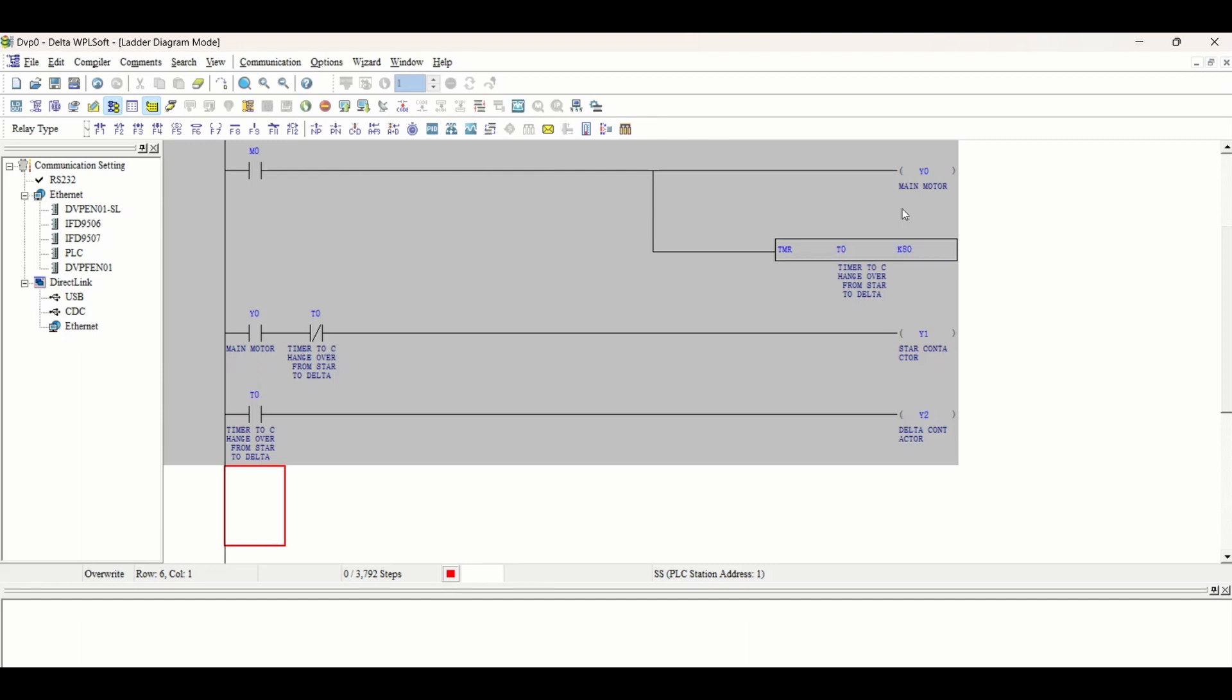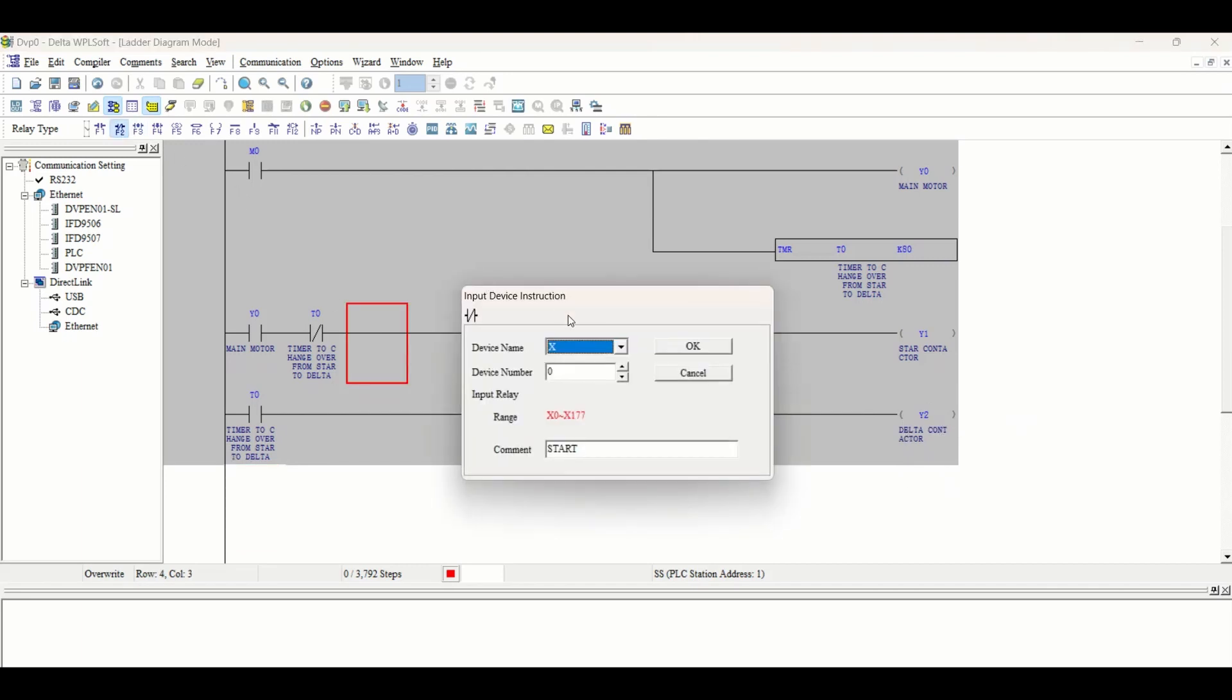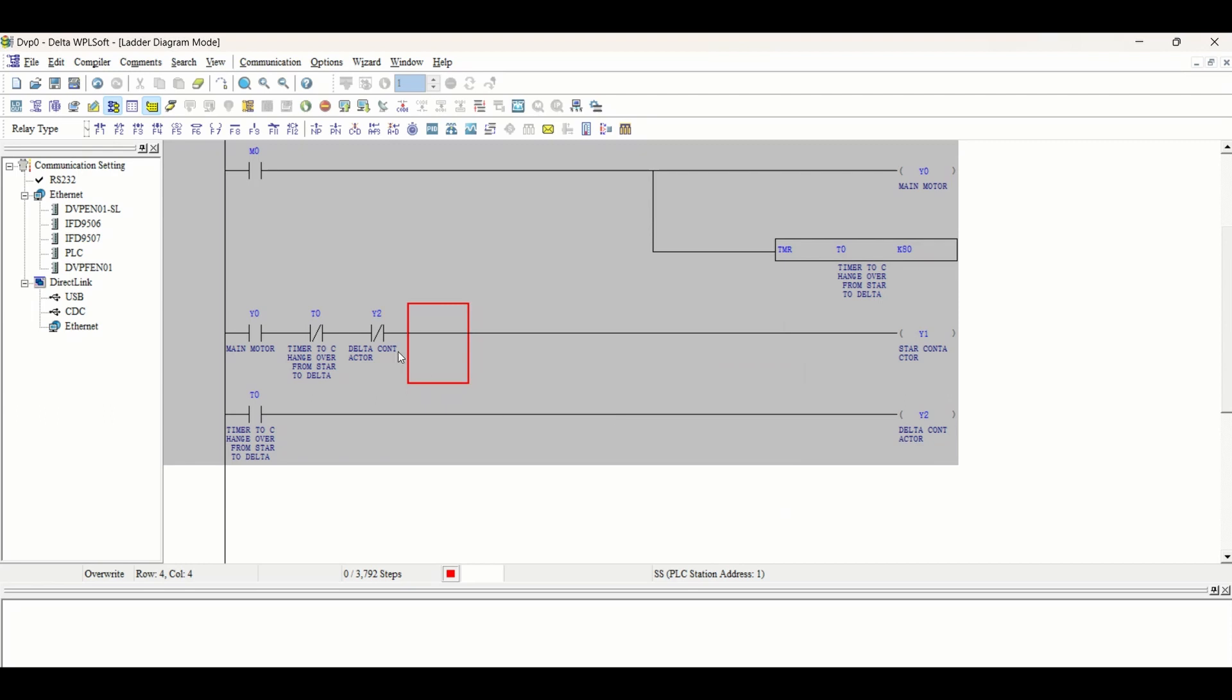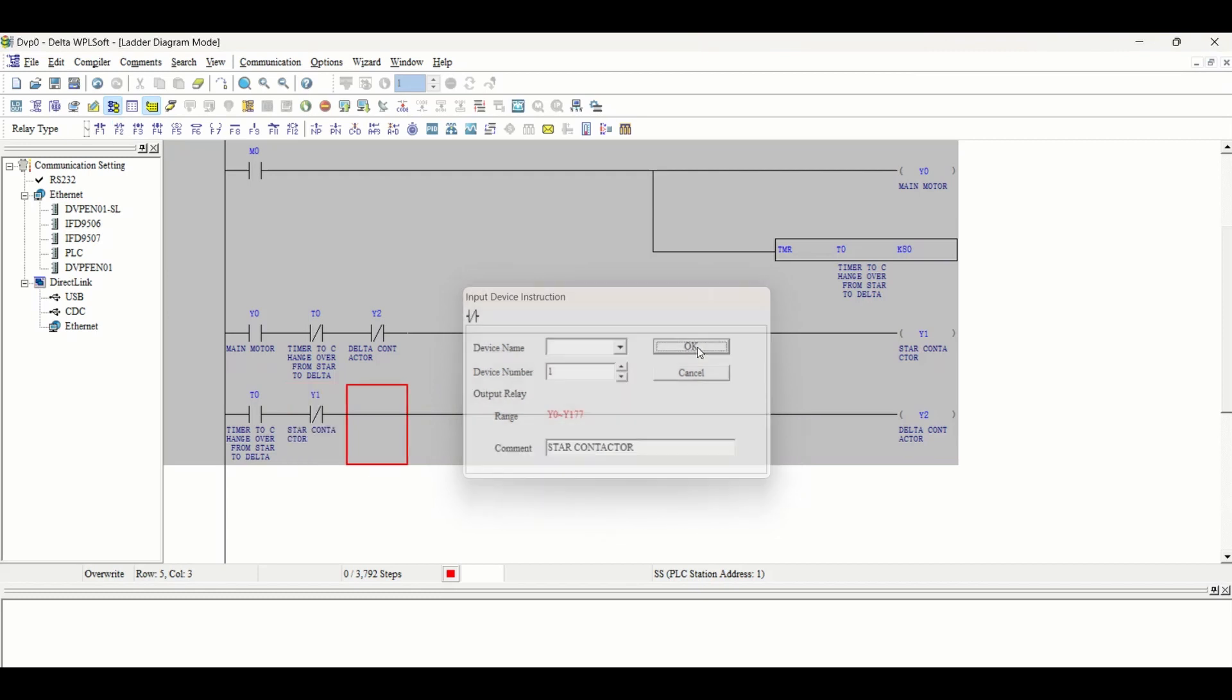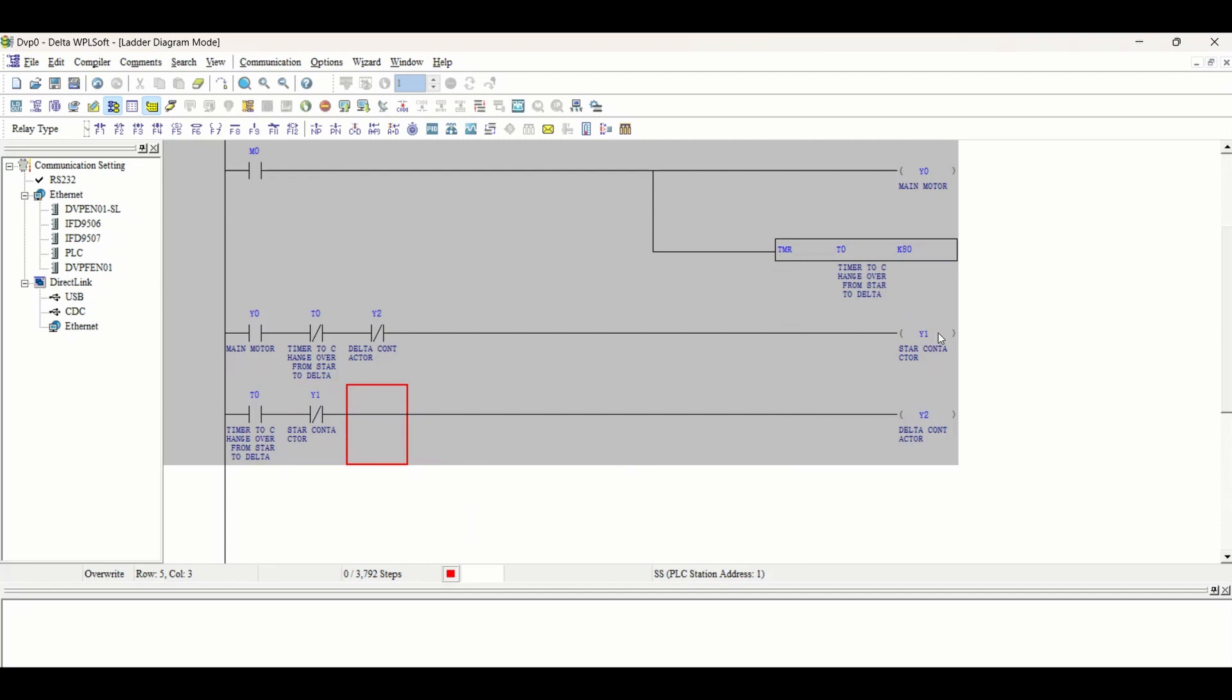There are also safety features we require. The star contactor will only start when delta contactor is off. We will take an NC of Y2. So star contactor will go high only if the delta contactor is off. Similarly, we will take another NC of Y1 so when star contactor is off, then only delta contactor will go high.